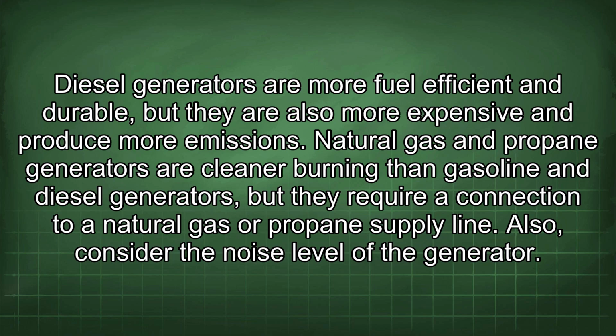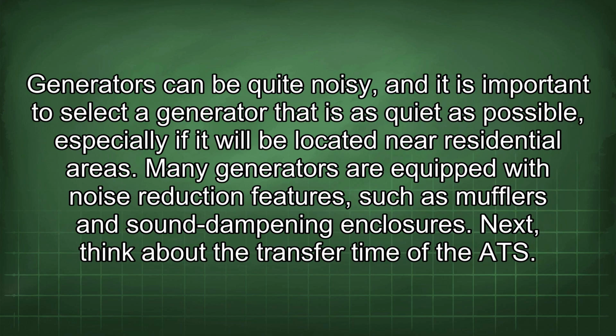Also, consider the noise level of the generator. Generators can be quite noisy, and it is important to select a generator that is as quiet as possible, especially if it will be located near residential areas. Many generators are equipped with noise reduction features, such as mufflers and sound dampening enclosures. Next, think about the transfer time of the ATS.